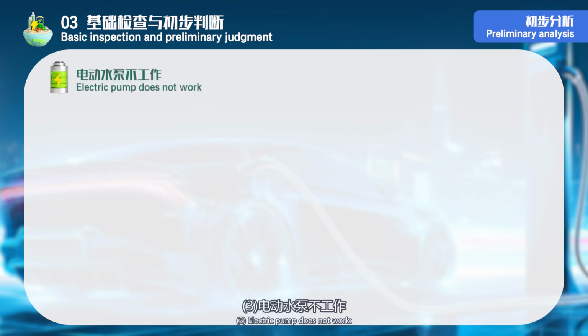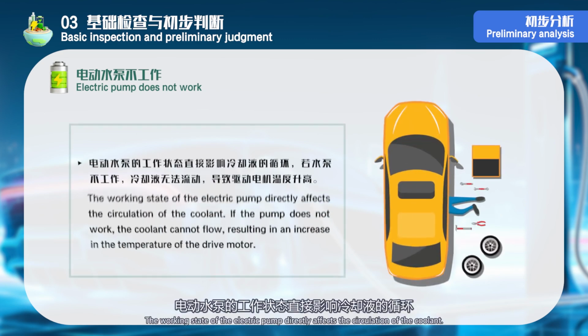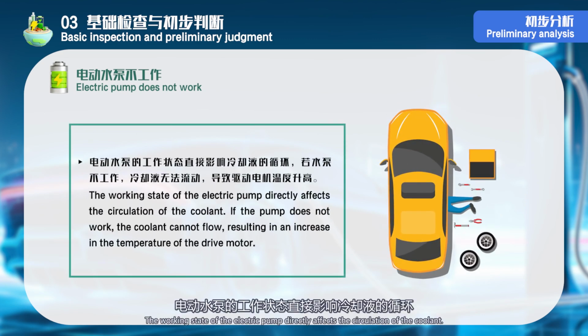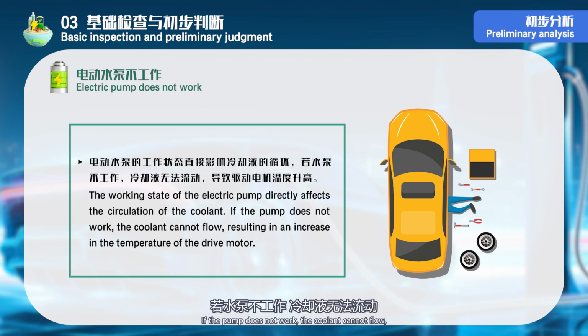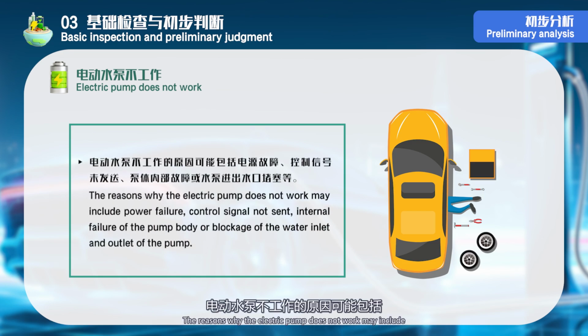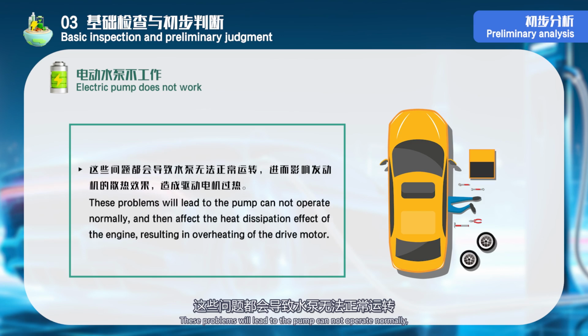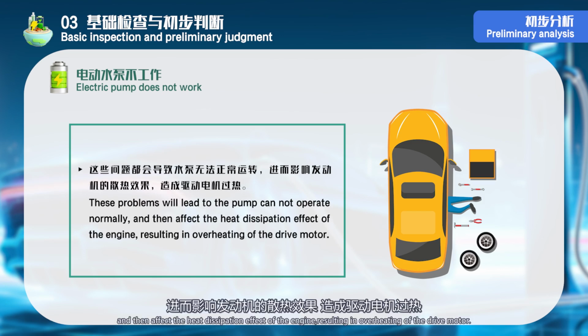3. The electric pump does not work. The working state of the electric pump directly affects the circulation of the coolant. If the pump does not work, the coolant cannot flow, resulting in an increase in the temperature of the drive motor. The reasons why the electric pump does not work may include power failure, control signal not sent, internal failure of the pump body, or blockage of the water inlet and outlet of the pump. These problems will prevent the pump from operating normally, and then affect the heat dissipation effect of the motor, resulting in overheating of the drive motor.